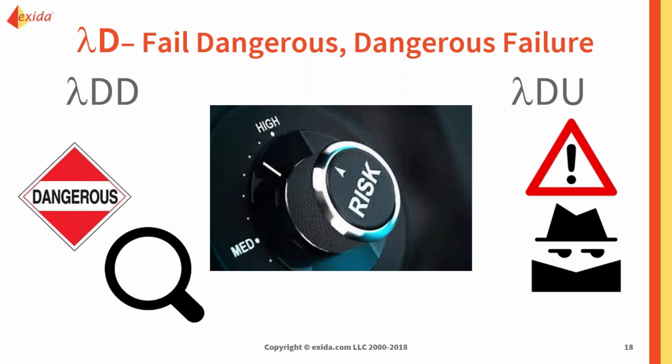Another example is a solenoid signal not alerting the actuator that it needs to energize or de-energize. What about a pressure sensor not sensing high pressure? Or a valve getting stuck in the open position if it's a close-on-trip application, or vice versa, that valve getting stuck closed when it needs to open. Or a transmitter shorting. And a transmitter shorting, depending on the situation, might always be undetected. Because in some cases, you might know about that transmitter shorting, but there's nothing you can do about it. So even though you know you're at a degraded state, you can't do anything to help.